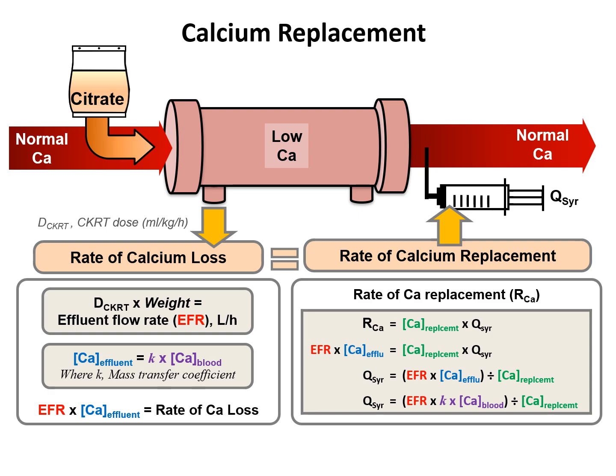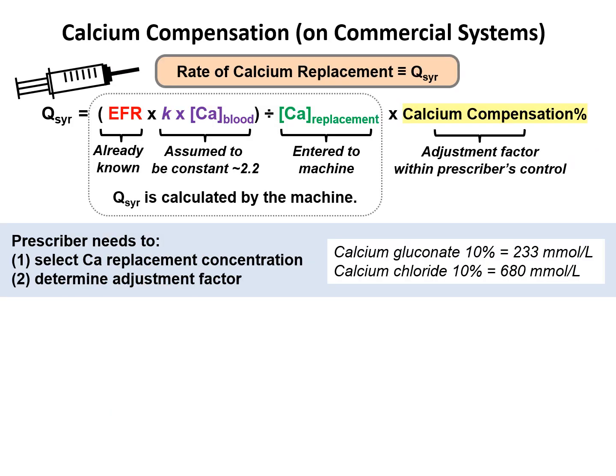These may look like a complex set of calculations, but most machines that handle regional citrate anticoagulation would have protocols to calculate the syringe flow rate of the calcium replacement fluid. Specific for Baxter systems, this is the formula embedded into the system. The effluent flow rate is already entered as part of the CKRT prescription. The prescriber needs to select the calcium replacement fluid concentration — quite often calcium gluconate 10%, with a calcium concentration of 233 millimoles per liter, or calcium chloride 10% with 680 millimoles per liter. The machine then calculates the syringe flow rate.